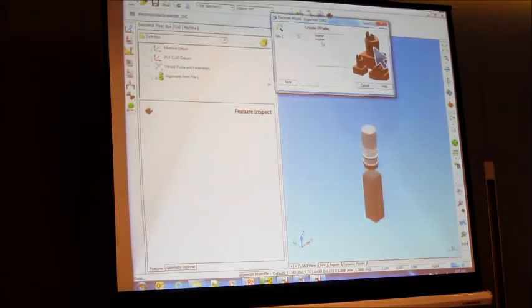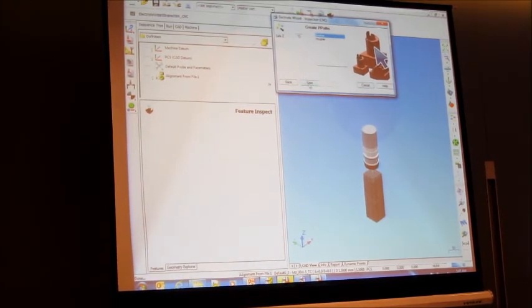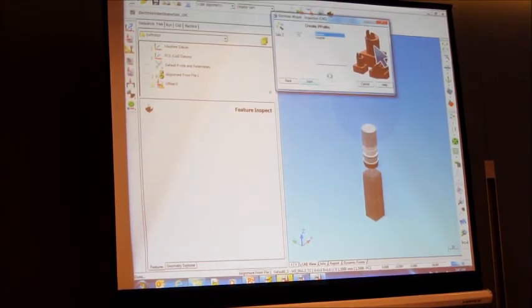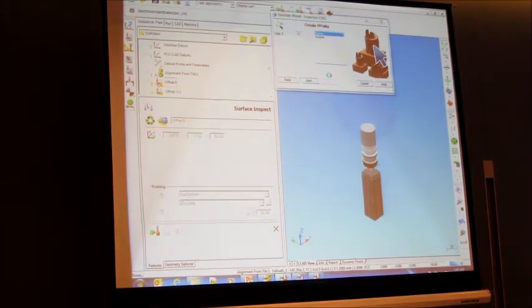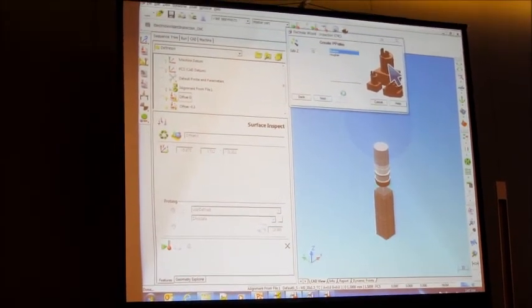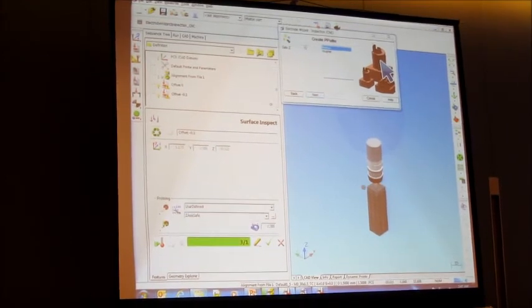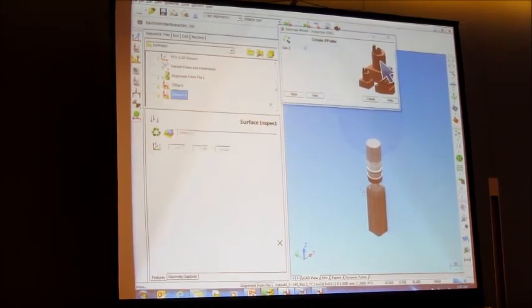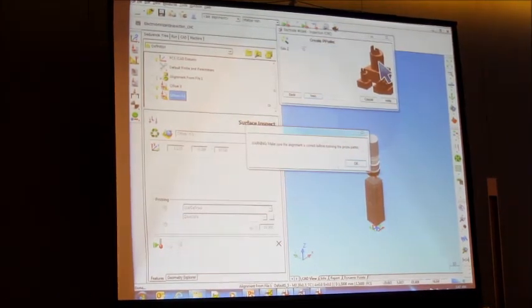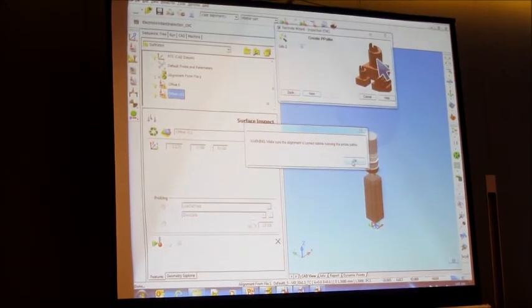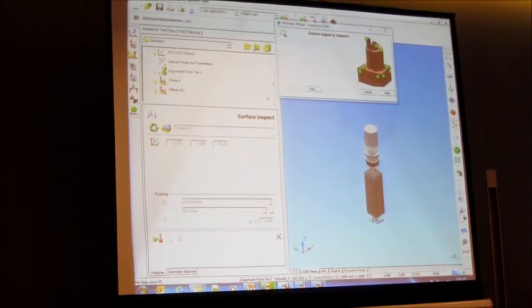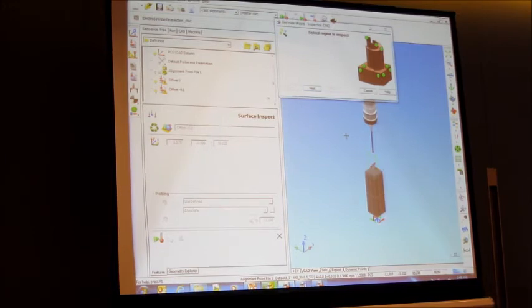So once it's loaded, we can select Finisher, and that will automatically load the probe paths that you saw us generate inside PowerShape. So the probe paths are automatically being loaded and created. Once we have those, it's warning us to make sure that we've got the alignment correct. So I'm just going to lift that probe out of the way and zoom in.